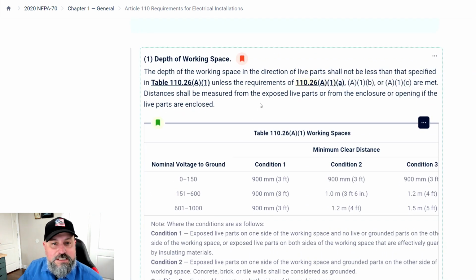The depth of working space in the direction of live parts shall not be less than is specified in Table 110.26(A)(1), unless the requirements of 110.26(A)(1)(a), (b), or (c) are met. Distance shall be measured from the exposed live parts or from the enclosure or opening if the live parts are enclosed. So there's been confusion on this in the past.